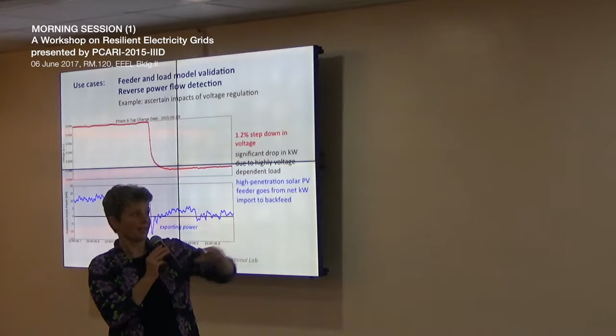The utility often wants to know how much power is produced by solar versus how much is load, because right now they only see the net power—the sum of the two—without knowing how much load is being masked by solar generation offsetting it. They'd want to know this for planning: what if there's a loss of generation from a disturbance, and suddenly they're faced with load they previously didn't see? What if they have to do a cold load pickup on that circuit? They don't know how much is behind it.